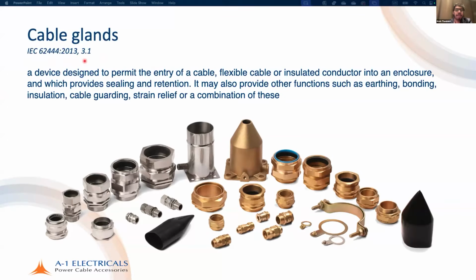A cable gland is a device which is designed to permit the entry of a cable, flexible cable or insulated conductor into an enclosure and which provides sealing and retention. So sealing and retention are very crucial. It may also provide other functions, for example, earthing, bonding, insulation, cable guarding, strain relief, or a combination of these. So it is required to provide sealing and retention, but as you will see, there is a wide variety of glands, and there are important functions such as earthing, bonding, and insulation that come into the picture.